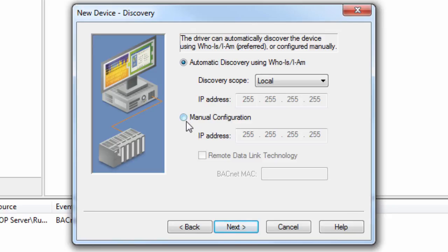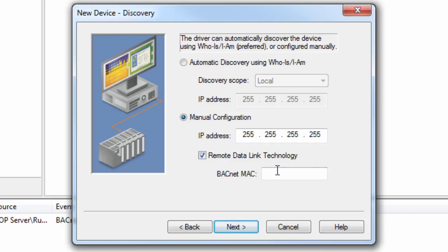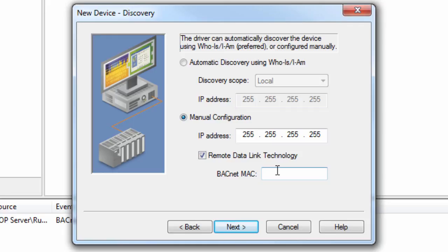If using manual configuration, there is an option for the driver to use Remote Data Link Technology. This parameter controls whether the driver automatically calculates the BACnet MAC for a BACnet IP device, or if the driver uses a hexed string for the BACnet MAC. If a device is on a remote subnet that uses a data link technology that is not BACnet IP, such as MS/TP, LonTalk, or ARCNET, the BACnet MAC must be entered manually, and the checkbox should be checked.